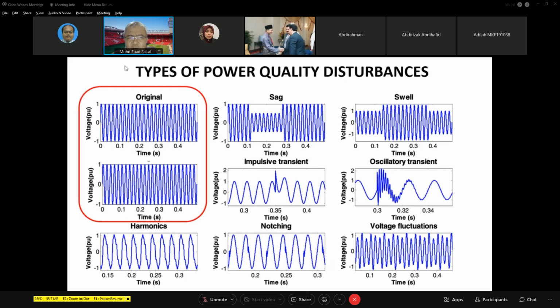The same also goes for voltage transient, as you can see on my slide. Impulsive transient, oscillatory transient. These are all of very short duration. The most common symptom: the light will blink. And then we have harmonics. As you can see, the voltage is no longer a sine wave, but distorted. Followed by notching. There are some small transients there. And next we have voltage fluctuation. These are basically the main ones. There are more power quality disturbances, but I'm showing you the main ones now.